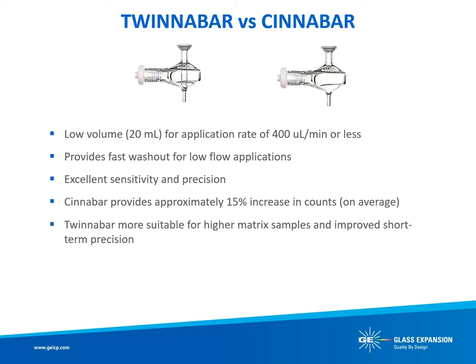The Cinnabar and Twinnabar are the low-volume 20 mL designs of the Tracy and Twister respectively. These low-volume designs are recommended for faster washout when an uptake rate of 0.4 mL per minute or less is employed. Like the Tracy, the Cinnabar will provide slightly higher sensitivity, whereas the Twinnabar, like the Twister, is more suitable for higher-matrix samples.